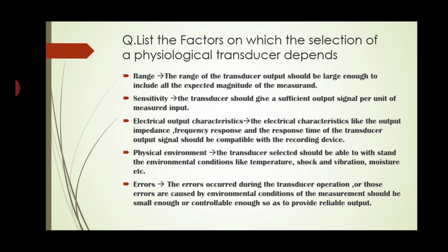Third is the electrical output characteristics. Electrical characteristics like the output impedance, frequency response, and the response time of the transducer output signal should be compatible with the recording device. Next, physical environment. The transducer selected should be able to withstand environmental conditions like temperature, shock, vibration, and moisture.